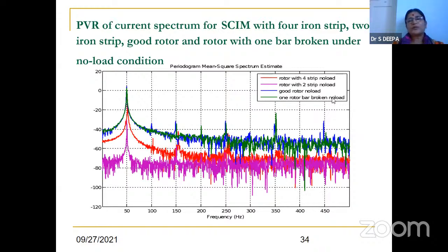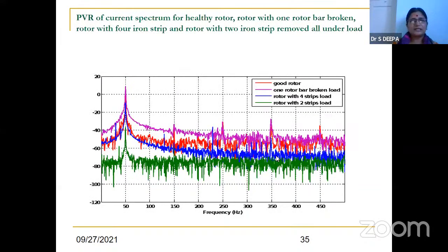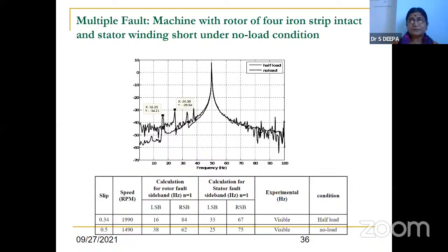So one rotor bar broken, no load, good rotor, no load, and rotor with 2 strips, no load, 4 strips, no load. So we'll study different patterns or signatures with and without load. So this is with the stator and the rotor fault. It's the multiple fault. So you'll have the frequencies for rotor as well as the stator fault occurring in the system; we can find at no load and the half load condition.